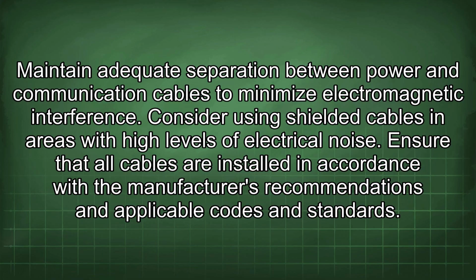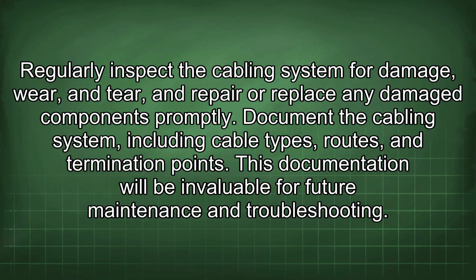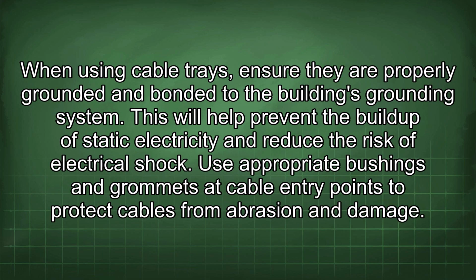Ensure that all cables are installed in accordance with the manufacturer's recommendations and applicable codes and standards. Regularly inspect the cabling system for damage, wear and tear, and repair or replace any damaged components promptly. Document the cabling system, including cable types, routes, and termination points. This documentation will be invaluable for future maintenance and troubleshooting. When using cable trays, ensure they are properly grounded and bonded to the building's grounding system. This will help prevent the buildup of static electricity and reduce the risk of electrical shock.